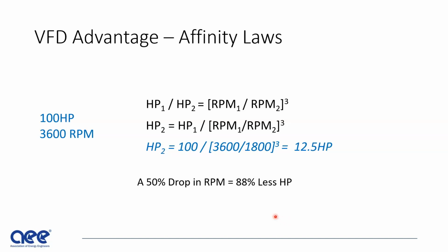So let's take a look at an example. Now I'm going to use real simple numbers here. Obviously, a motor doesn't operate at 3,600. It's going to be 3,565 or some number. But I'm just going to use the synchronous numbers at 3,600 and 1,800 to keep the example really, really simple. If we cut the RPM by half, so we're using a VFD to reduce the CFM or the RPM by half, then here's the equation. We have 100 divided by 2 cubed, which is 12.5 horsepower. So you go from 100 horsepower to 12.5 horsepower by cutting the RPM in half. Very dramatic.